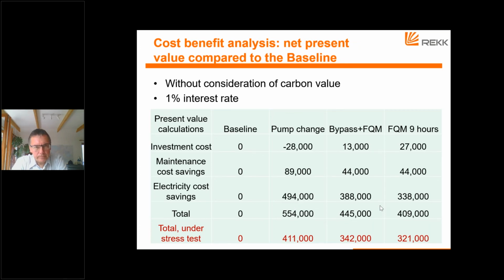So putting all the pieces together, comparing to the baseline, these are our figures. Concerning investment cost, the baseline would have some reconstruction cost, but compared to the baseline there is no shift. Buying the new pump would still result in cost, so cost items have a negative sign. However, the other two technologies would be less expensive in present value terms than the baseline reconstruction cost, so there are already some savings there. Looking at maintenance costs, there are continued additional savings, and electricity costs again show savings. Here we assume a 1% discount rate. Altogether, the value of these scenarios is between 400,000 and 550,000 euros for the Novi Sad Water Utility company.